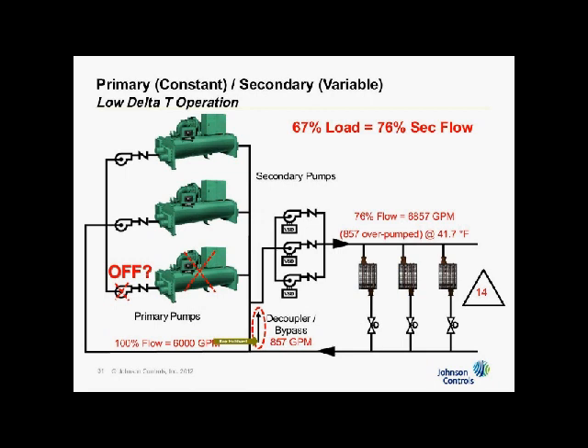That 857 now mixes 54 degrees into the 40 degrees that's up here, delivering a mixed temperature of 41.7. The 41.7 goes out to all the coils. The coils see 41.7 instead of 40. They've got to open the valve more, so then it comes back warmer, and it keeps doing this until it cycles completely out of control. Right? So it's very important to keep enough flow so that you don't have this backflow happening.